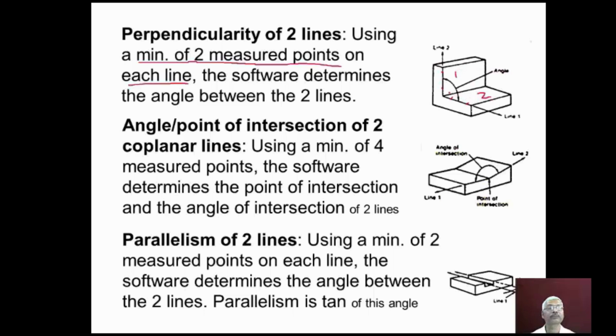lines or planes. Angle of intersection, a point of intersection of 2 coplanar lines. Using a minimum of 4 measured points, software determines the point of intersection. So here we should give 2 points, and on the line 2 we should give 2 points, and software will determine the point of intersection. So coordinates of point of intersection can be calculated, and the angle of intersection of 2, this angle also can be calculated. Then parallelism of 2 lines.